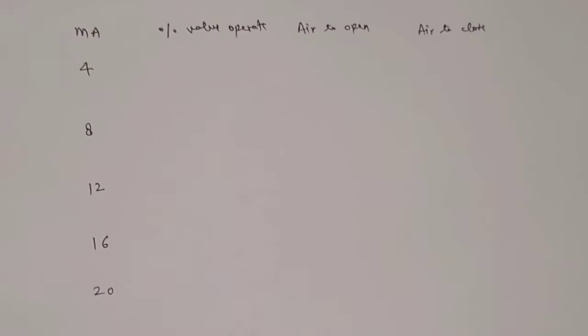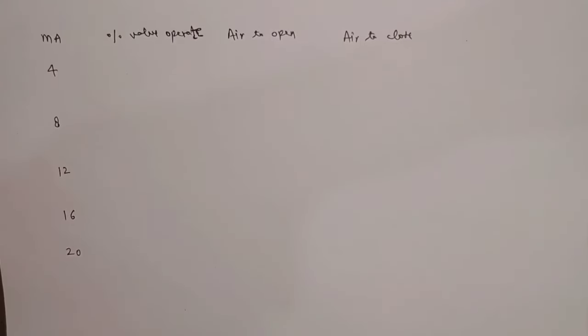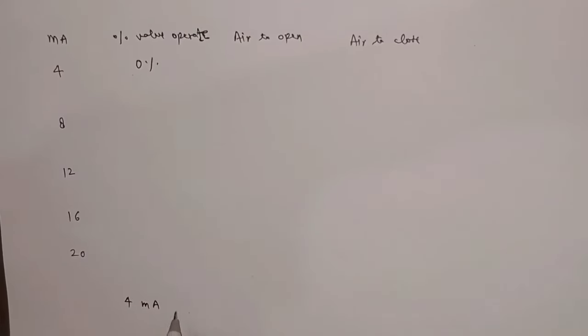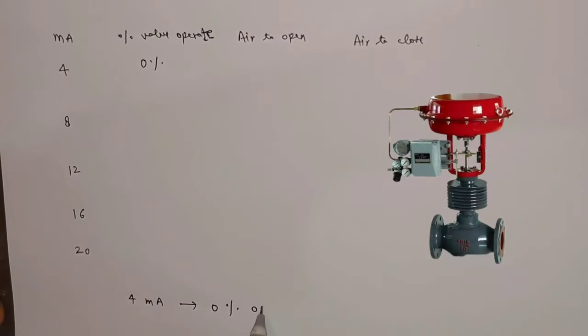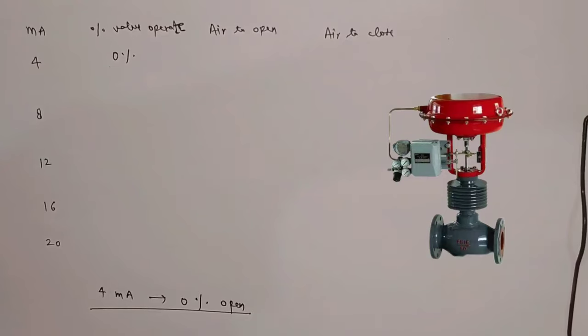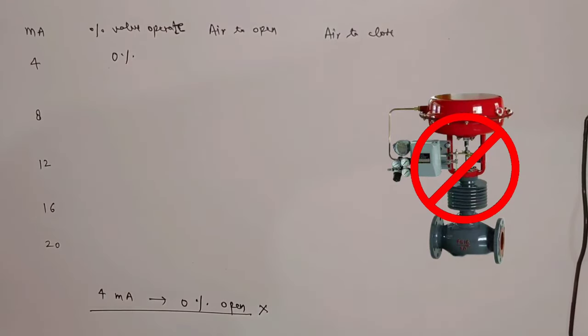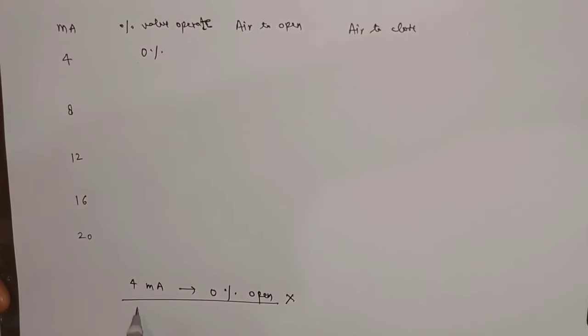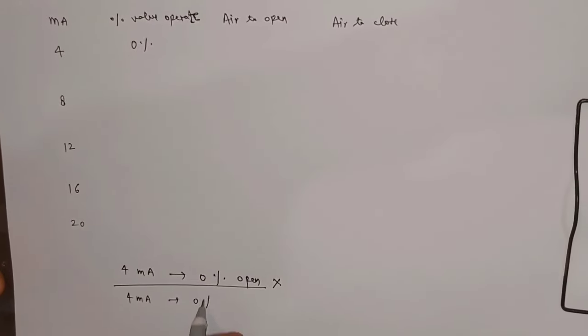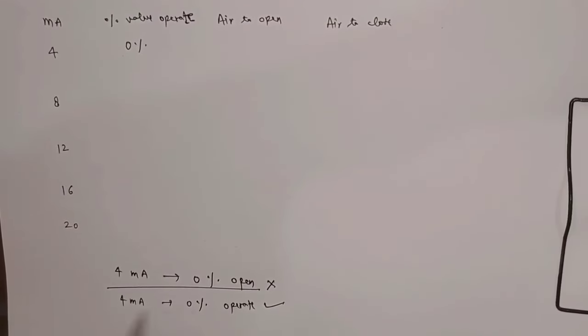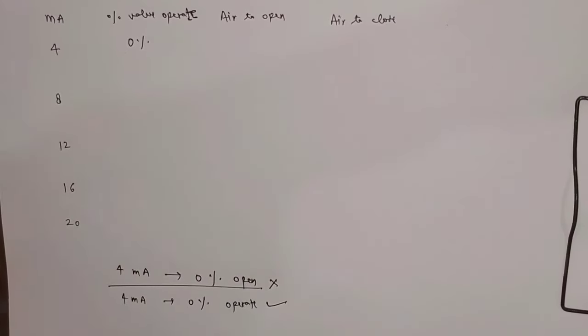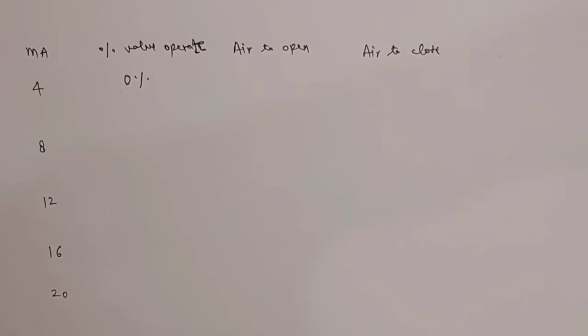Let's understand it further. Look friends, at 4 milliampere, the valve operates at 0%. Here you need to keep one concept in mind. At 4 milliampere, many people think that valve opening is 0%, but this is not applicable on all control valves. You can say it like this: at 4 milliampere, the control valve will operate 0%. That sentence is correct — not that at 4 milliampere the valve will open 0%. With this concept, you will understand everything.